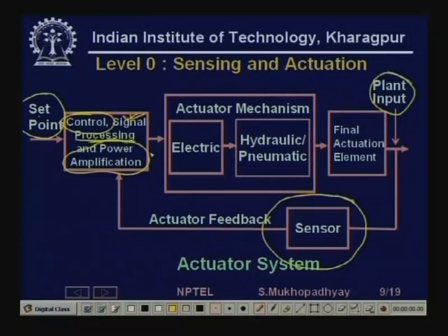And obviously, some amount of electrical power amplification is done. So you use what are known as servo amplifiers. Servo amplifiers take weak signals and accurately, exactly proportionally multiply them, but with a lot of power amplification. Now, in an actuator so much power amplification is necessary that it is always done in stages. First, one level of power amplification at the electrical level, where you take one electrical signal and increase its electrical power. After that, if you want to increase power further, often we go to different forms of energy.